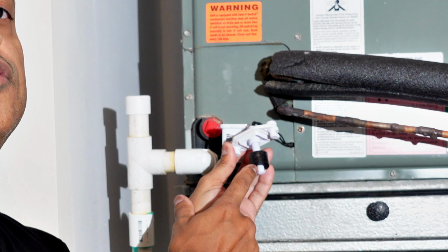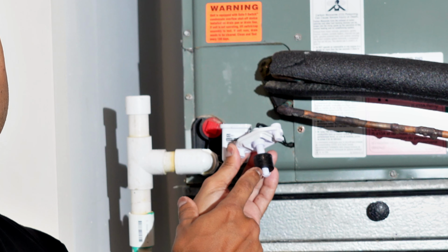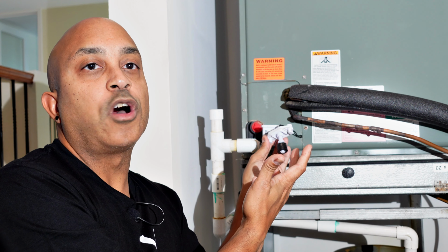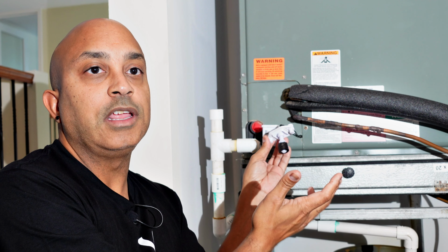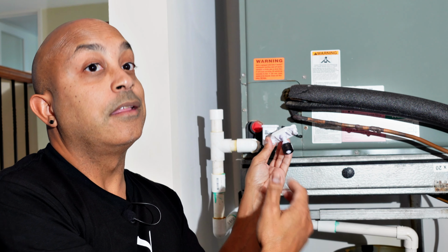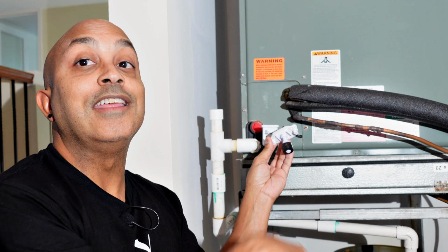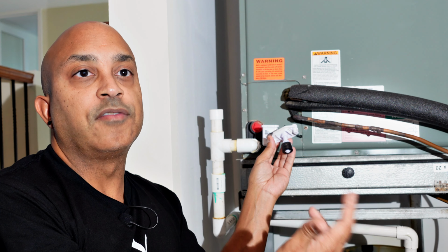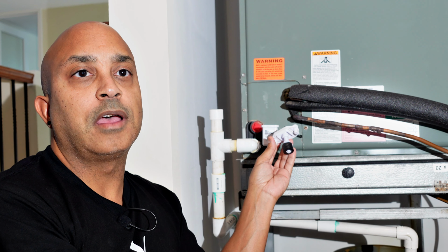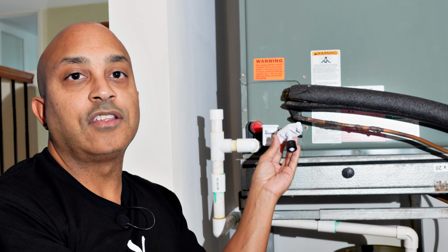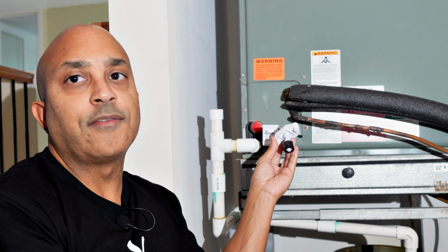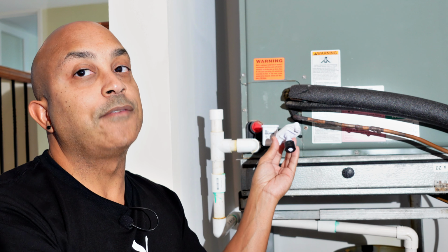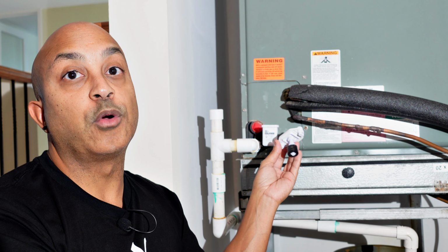And what this switch does is it kills the power to your AC unit. And when that happens, your AC shuts off and there's no more water accumulating, so there's no more leaks, which tells you, hey, there's something going on with my drain. I need to clean my drain. And that will stop the leaks and prevent you guys from having a mess from time to time. Yes, it's an inconvenience because your AC is off, but if you have expensive flooring, wood floor or something like that, it's a better alternative than having to rip out your floor or having warped floorboards.